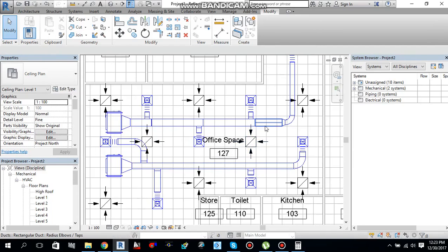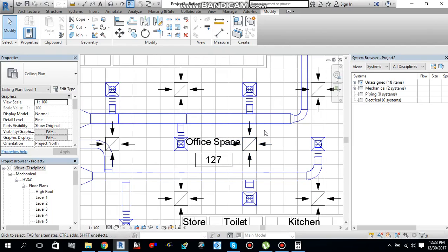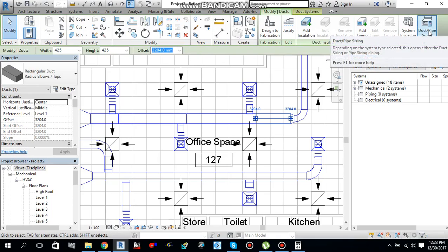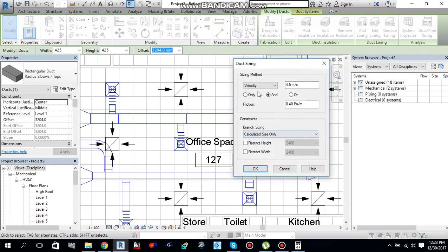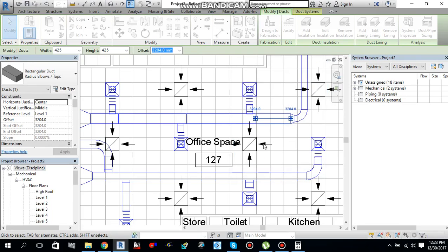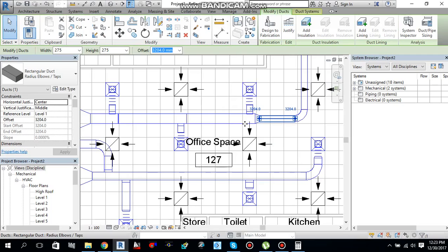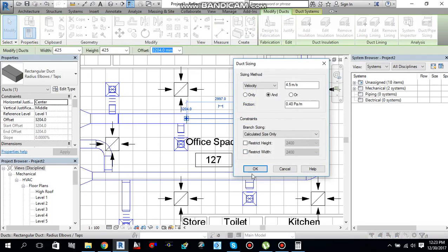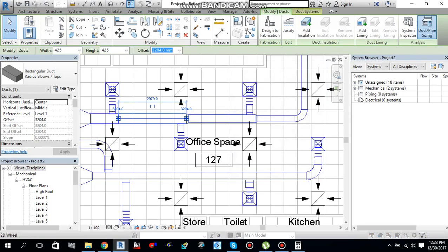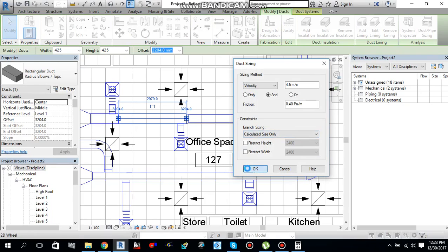One thing you can do is perform duct sizing on a single piece of duct. For example, select this duct piece and do Duct/Pipe Sizing — same method: 4.5 meters per second maximum velocity, maximum friction 0.40 Pascal per meter, say OK. It will resize the duct. You can perform duct sizing on each piece using the same method.